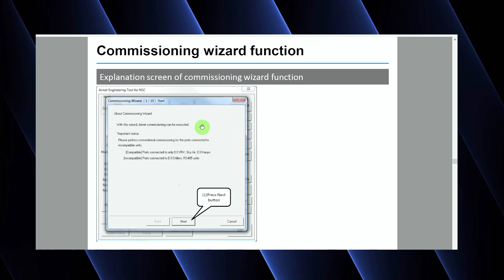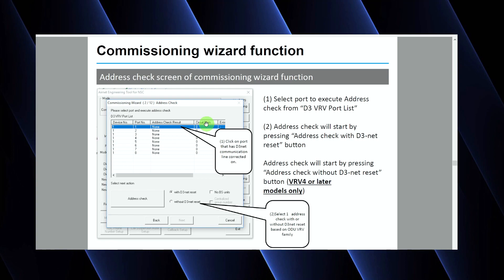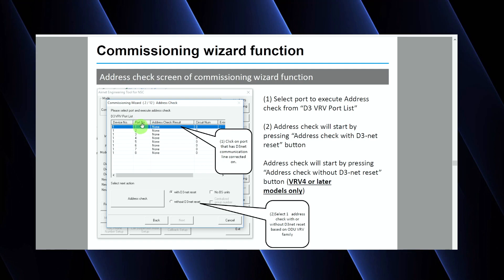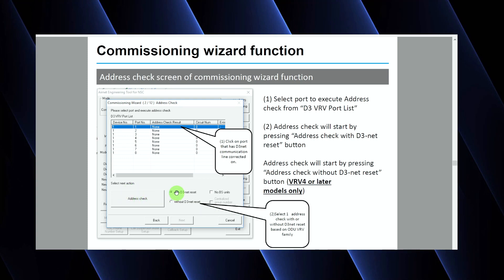It says you're about to do the commissioning wizard. Just click the 'Next' button — it's going to take you to the next step. The next step is where you're going to have to have the system verify the port of the ITM. What it's going to basically do is scan port one. So if you had your ITM with all the wires hooked up to the back of it, port one is going to be the back of the ITM. If you had an expansion module, that's port two, three, four, however many you had. Click the port that you want to check and then hit 'Address Check.' Sometimes it will error out depending on the version of VRV that you have — sometimes you will have to click 'Without D3 Net Reset' and then click address check. But for the most part, you're going to click 'With D3 Net Reset,' click address check, and then go to the next step.